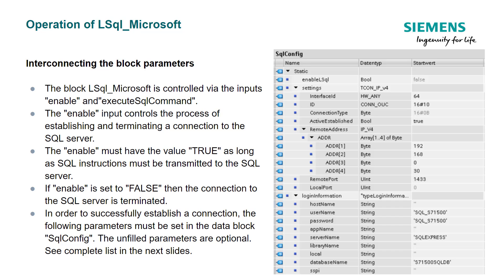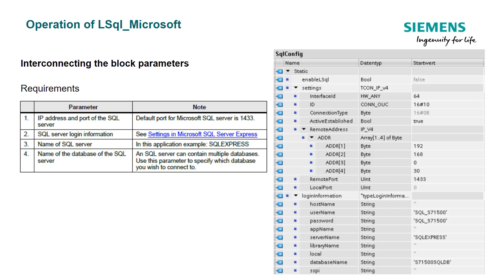The block LSQL Microsoft is controlled via the inputs enable and execute SQL command. The enable input controls the process of establishing and terminating a connection to the SQL server. Enable must have the value true as long as the SQL instruction must be transmitted. If enable is set to false, the connection to the SQL server is terminated. To successfully establish a connection, the following parameters must be set in the data block SQL config. These include the IP address and the port of the SQL server — the default port for Microsoft SQL Server is 1433.